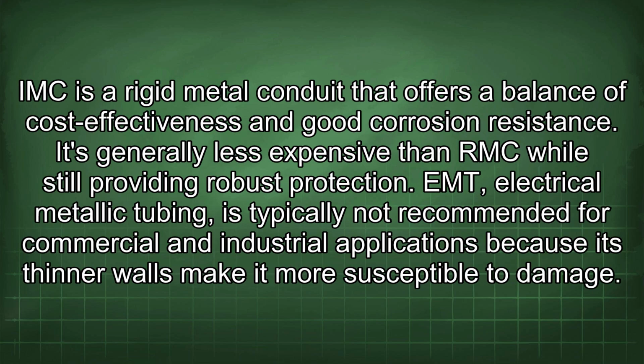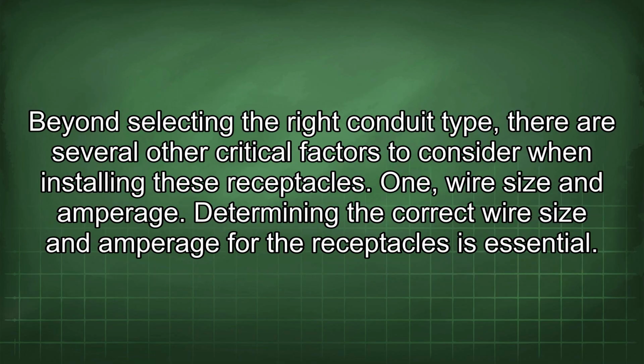IMC is a rigid metal conduit that offers a balance of cost-effectiveness and good corrosion resistance. It's generally less expensive than RMC while still providing robust protection. Electrical metallic tubing is typically not recommended for commercial and industrial applications because its thinner walls make it more susceptible to damage. Beyond selecting the right conduit type, there are several other critical factors to consider when installing these receptacles.